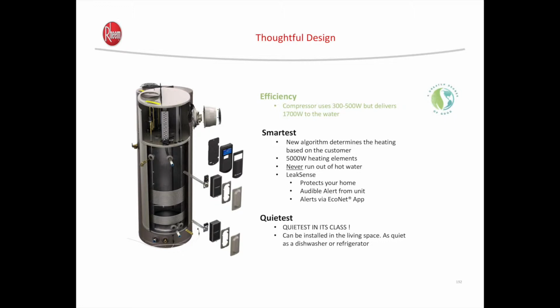The heat pump side of this thing that they're talking about, the ambient temperature range for this is anywhere from 37 to 140 degrees. One of the things I think Mike was telling me, somebody talked about earlier with heat pump water heaters, is that they cool down the area, the space, and they do. This will cool it down about 15 degrees, I think is what they said. What you can do with that, though, ours is completely ductable. It's duct ready, 5-inch coiled or flex duct.